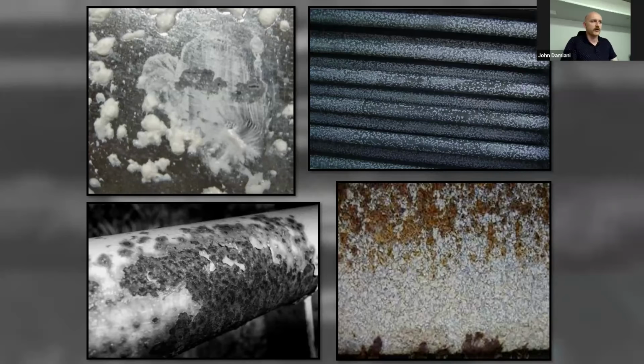It can also transport and deposit elsewhere, but these are definitely signs of problems, you do not want to see this because it's a form of corrosion. Most water treatment programs won't have any zinc component added, so if you're collecting samples of unknown substances in your cooling towers that turn out to have a high portion of zinc, it's probably coming off the galvanized coating in the tower. This is not reversible, it's corrosion, so you want to do everything you can to avoid it up front.